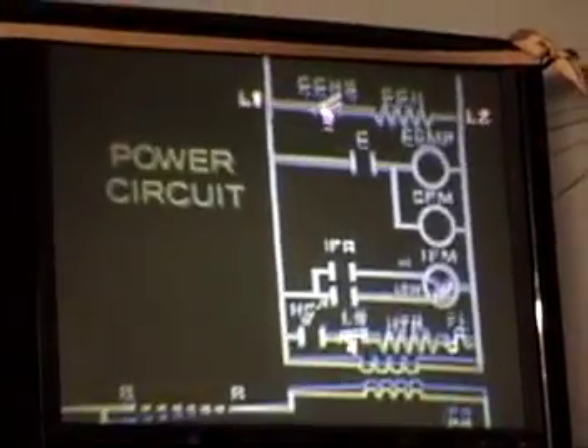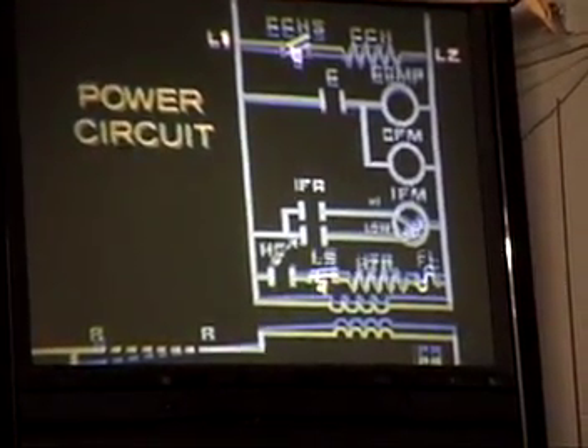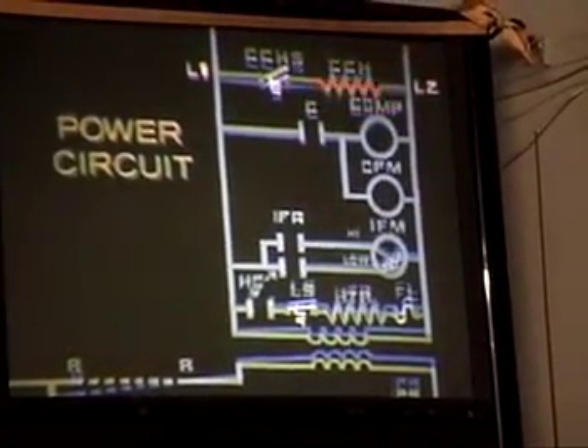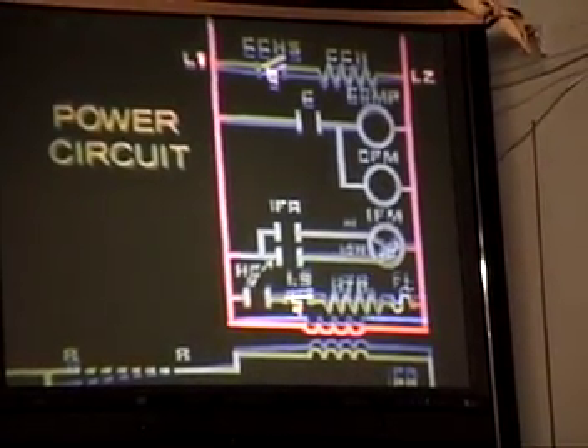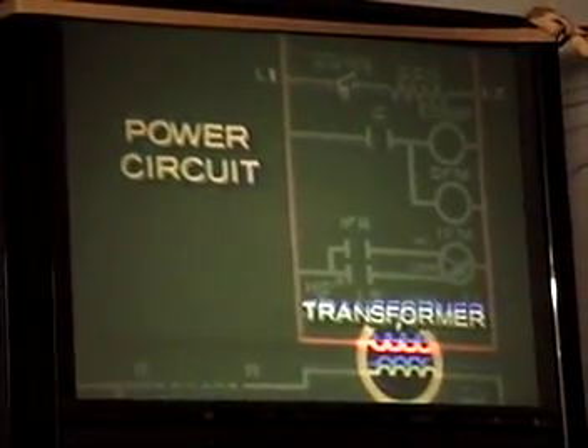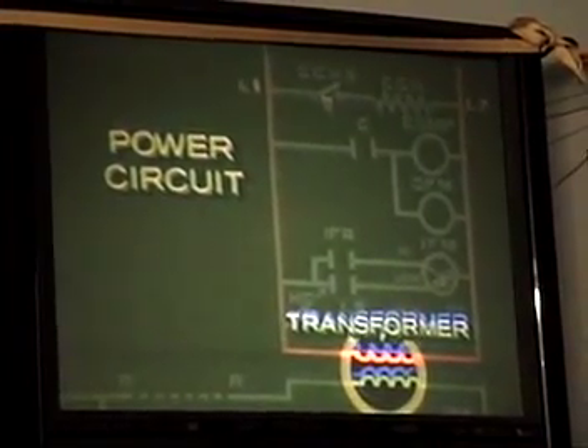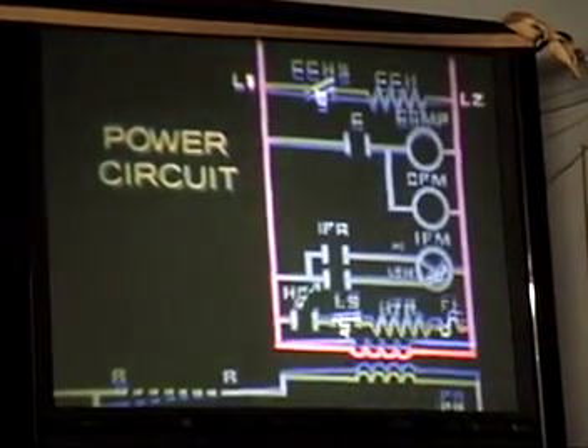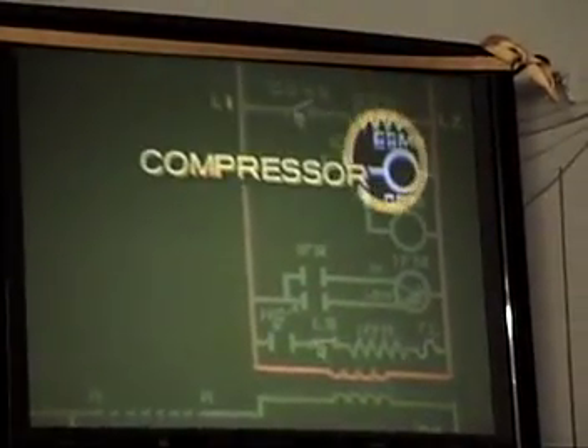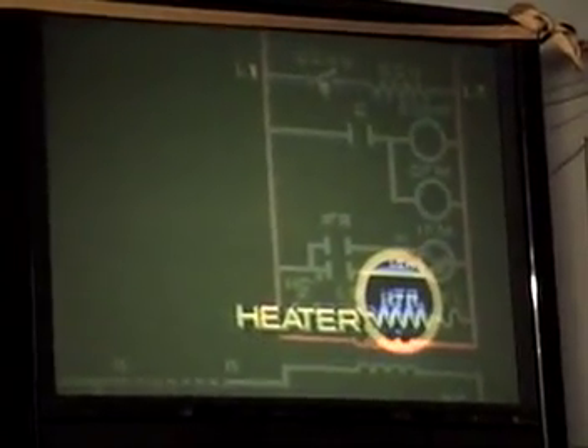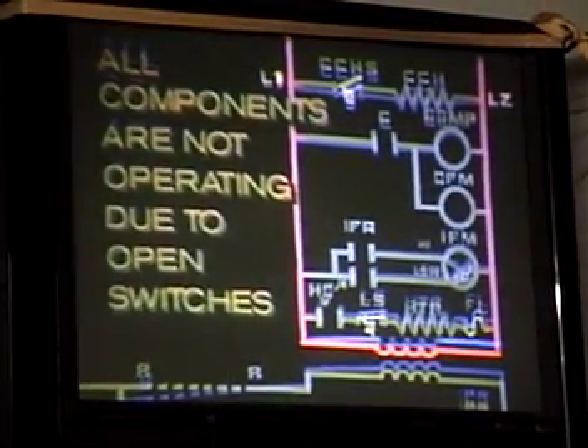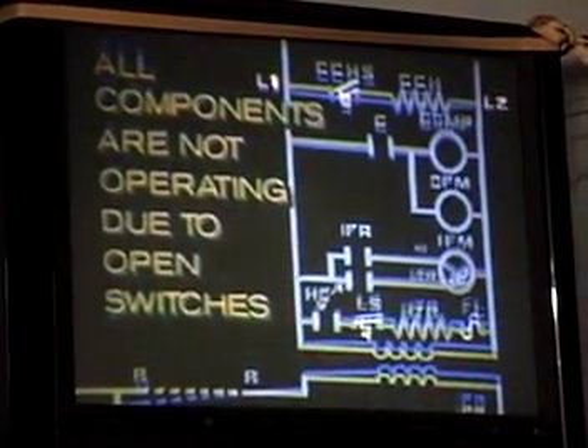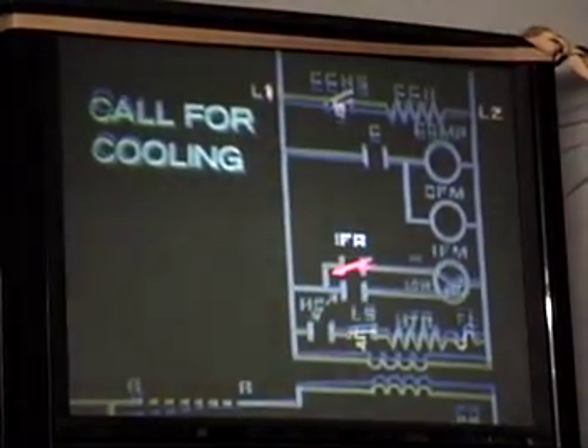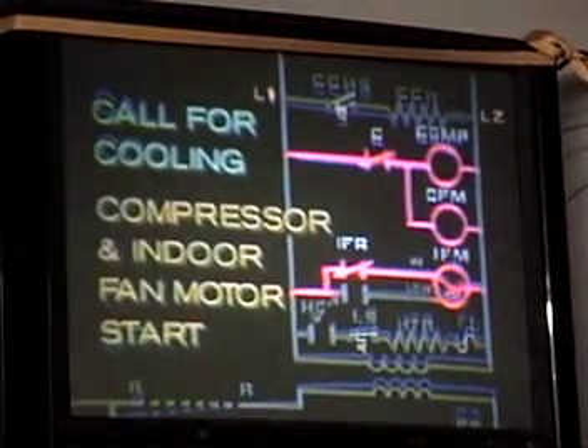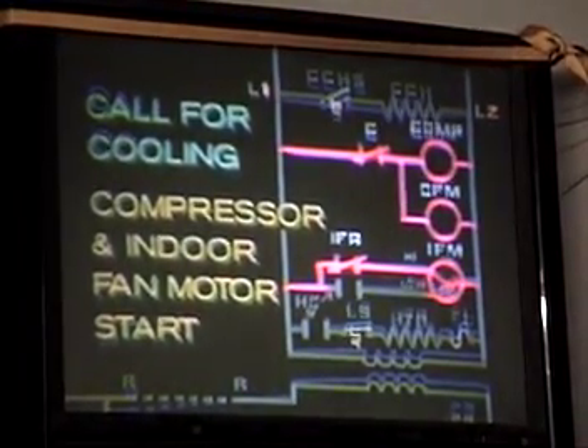The power circuit carries all the large electrical loads such as compressors, fan motors, and heaters, as well as supplying the primary side of the transformer. As long as power is connected, there will be voltage available at the primary side of the transformer. The crankcase heater, compressor, outdoor fan motor, indoor fan motor, or heater are not operating because open switches or controls interrupt the electron flow to the components. If we close the contacts, there will be power flow and the loads will operate.